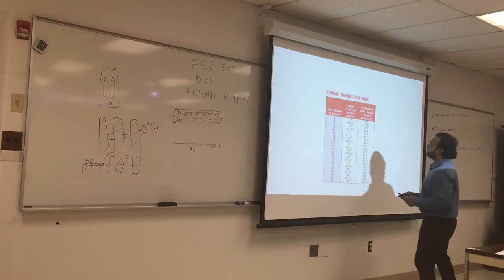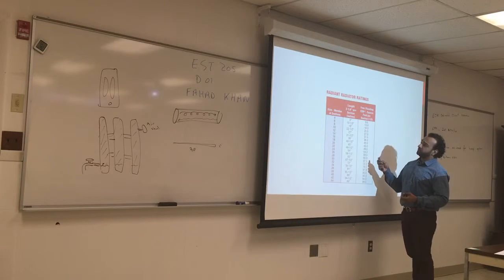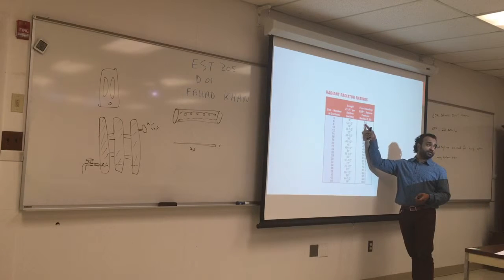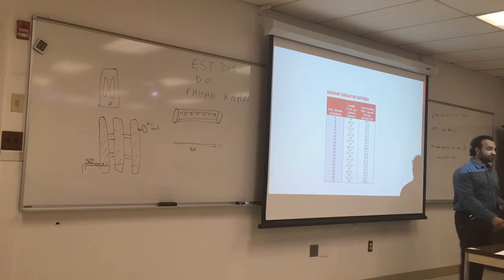This is the length per section, so they give you a length per section, and it will tell you the EDR per feet in each section. So if the section is 9 EDRs, how many BTUs is 9 EDRs? If I want to change 9 EDR, you multiply by 240. And you'll see how those radiators make heating much easier. They give off a lot of heat.